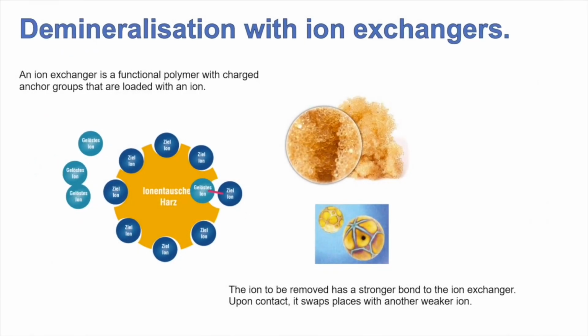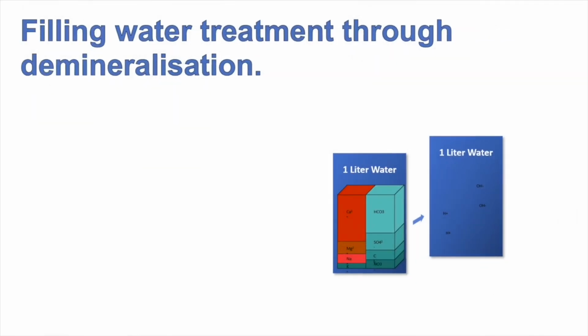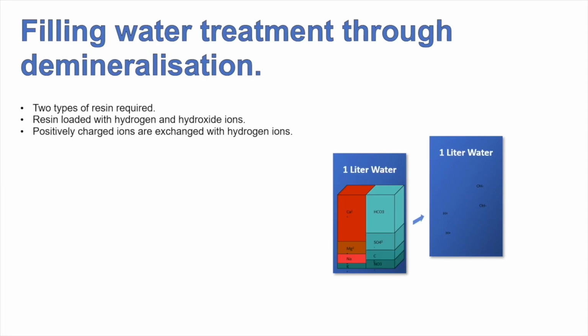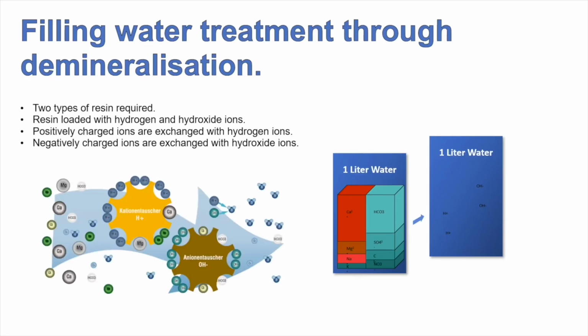So resin is made up of polymer beads. The polymer beads have different charges, and this is what attracts the different ions within the water. Filling water treatment through demineralization. Two types of resin are required: resin loaded with hydrogen and hydroxide ions. Positively charged ions are exchanged with hydrogen ions, and negatively charged ions are exchanged with hydroxide ions.